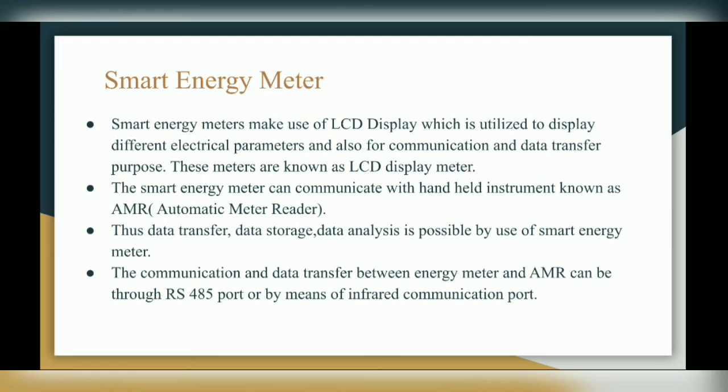The smart energy meter can communicate with a handheld instrument known as AMR, that is automatic meter reader. Thus data transfer, data storage, and data analysis are possible by use of the smart energy meter. The communication and data transfer between the energy meter and AMR can be through an RS-485 port or by means of an infrared communication port.